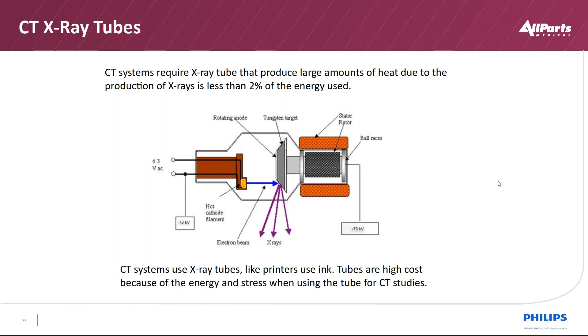So another item on the rotate frame would be the inverter here, driving the high voltage tank. That's a multiplier to get us that 140,000 volts. And then we would be spinning the X-ray tube anode as well, and controlling the filament temperatures with regards to how much mA we need for image quality. And then we have our detector that is hidden behind that light seal plate here. But the crystals have to be maintained at a pretty consistent temperature. Their transfer or leakage current would change a little bit based on temperature. So we have a temperature regulated detector. And then we have the A to Ds behind it. In this case, 64 slice system. Each of those rows has 64 crystal elements as far as depth on Z as well.